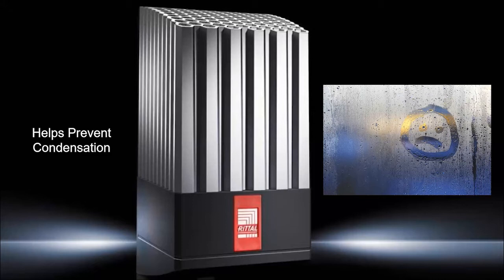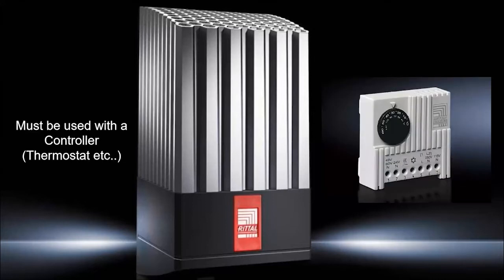And finally, number three is more of a reminder. When specifying an enclosure heater, you must partner it with some sort of controller so it knows when to activate. This could be a thermostat, which looks at the temperature inside the enclosure, or a hygrostat, which looks more at the relative humidity inside the enclosure and will activate it that way.